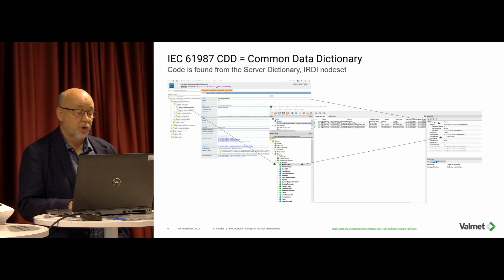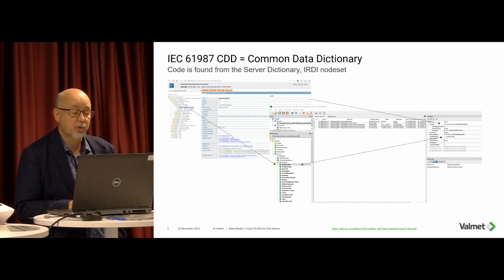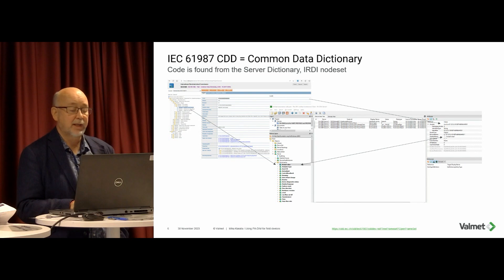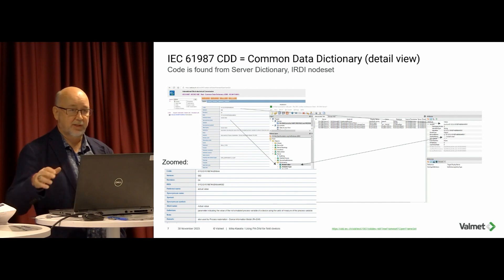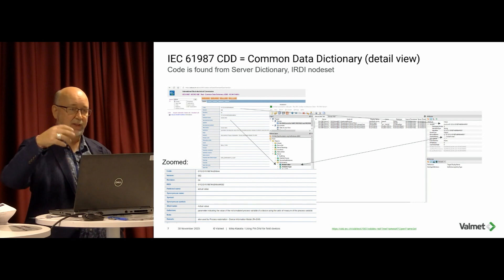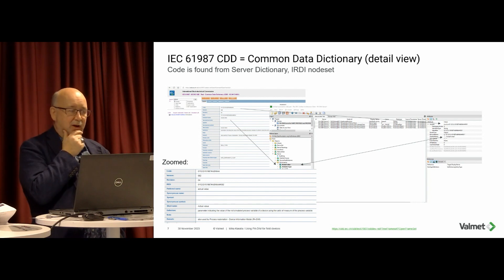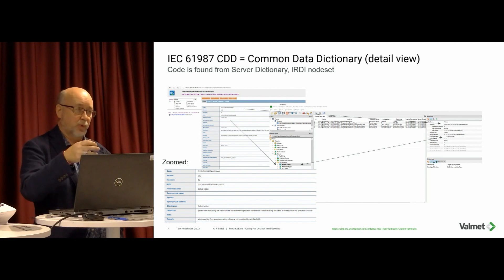On the IEC web pages you can look up the actual value, and here in UA Expert the display name is the actual value. The node ID is using the IEC specification code — I have a zoomed version here — and the code binds the actual value to the dictionary as a hash dictionary entry in the variable you are using. That is how the IRDI node set is bound into the PA-DIM, and that is the key point here.